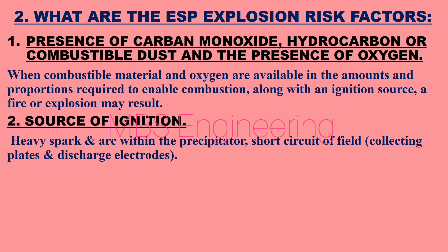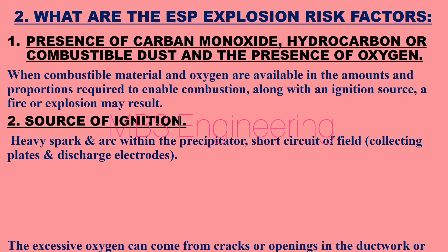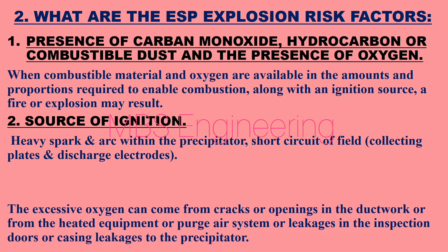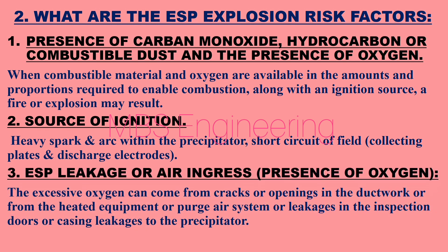Risk Factor 2: Source of ignition — heavy sparks and arcing within the precipitator, and short circuits between collecting plates and discharge electrodes. Risk Factor 3: ESP leakage or air ingress — presence of oxygen. Excessive oxygen can come from cracks or openings in the ductwork, from heated equipment, the purge air system, or openings in the inspection doors or casing leakages to the precipitator.